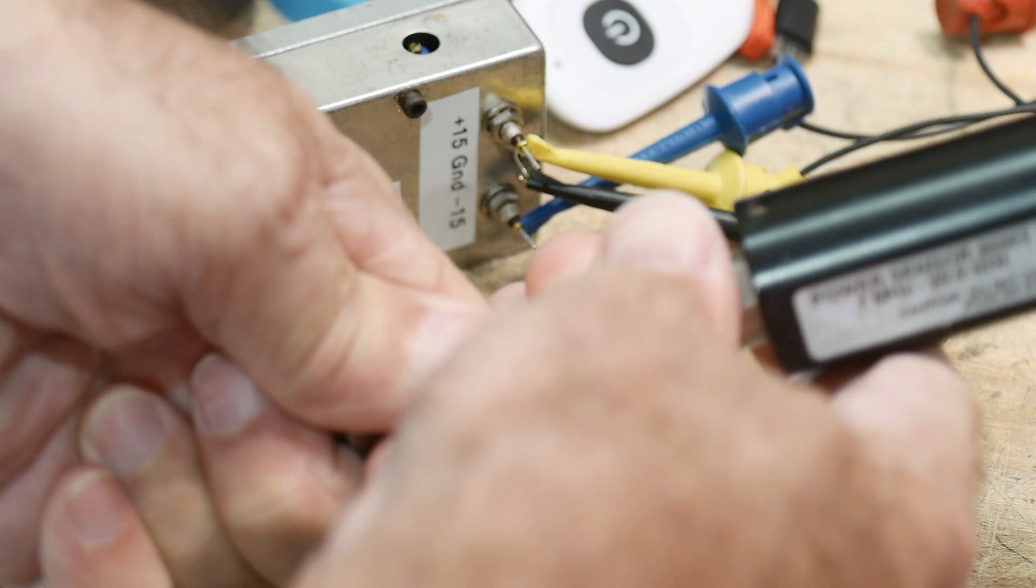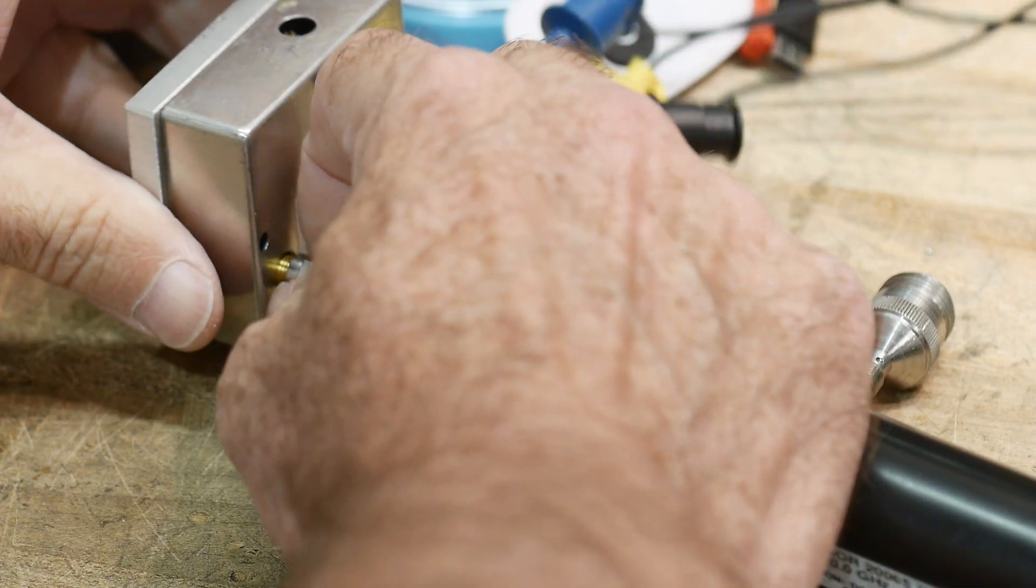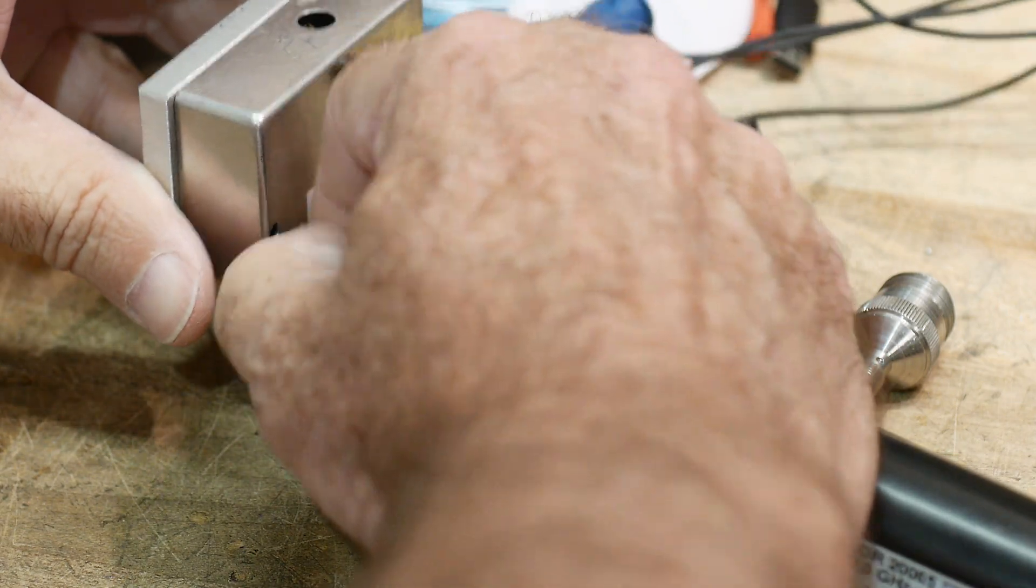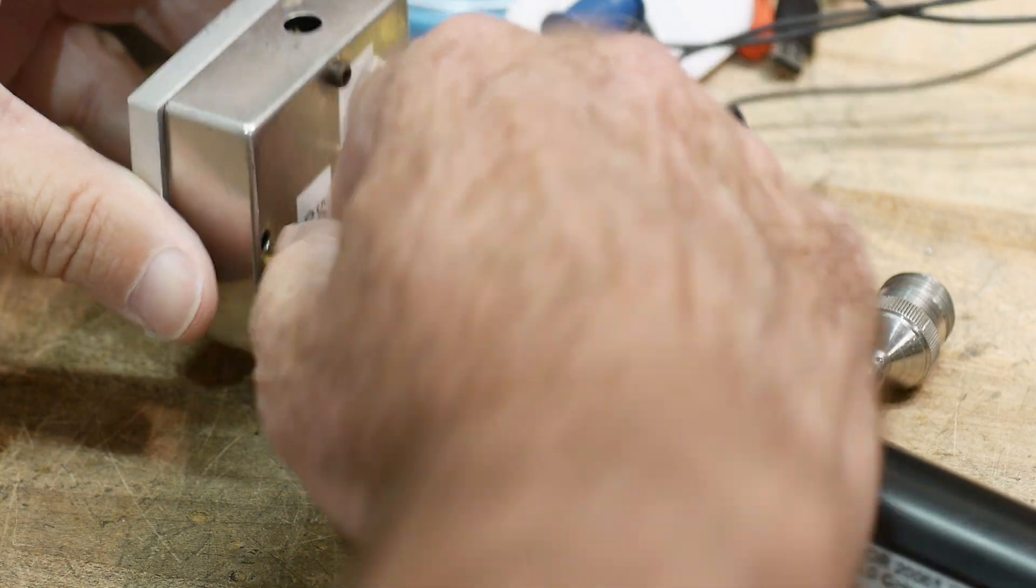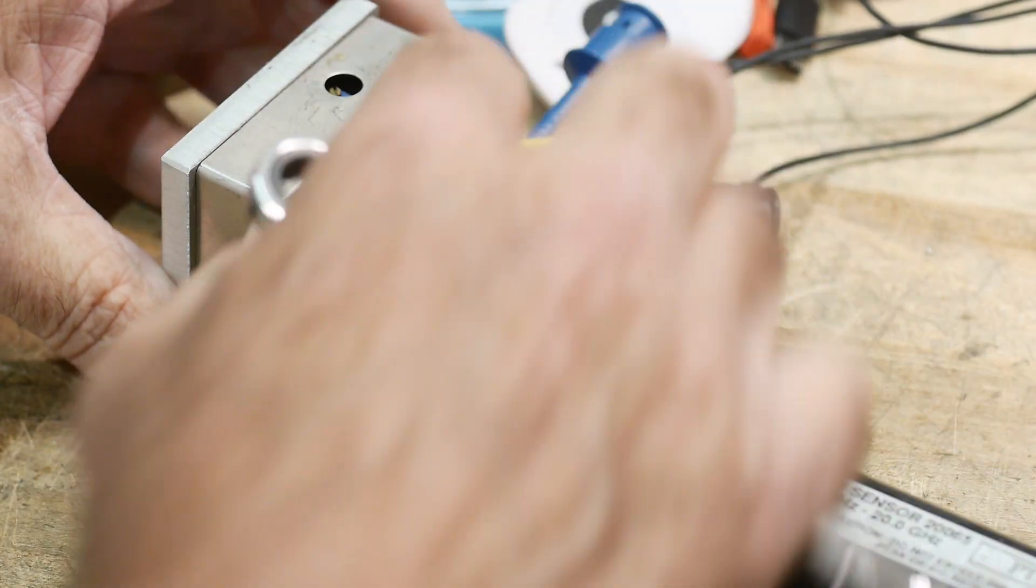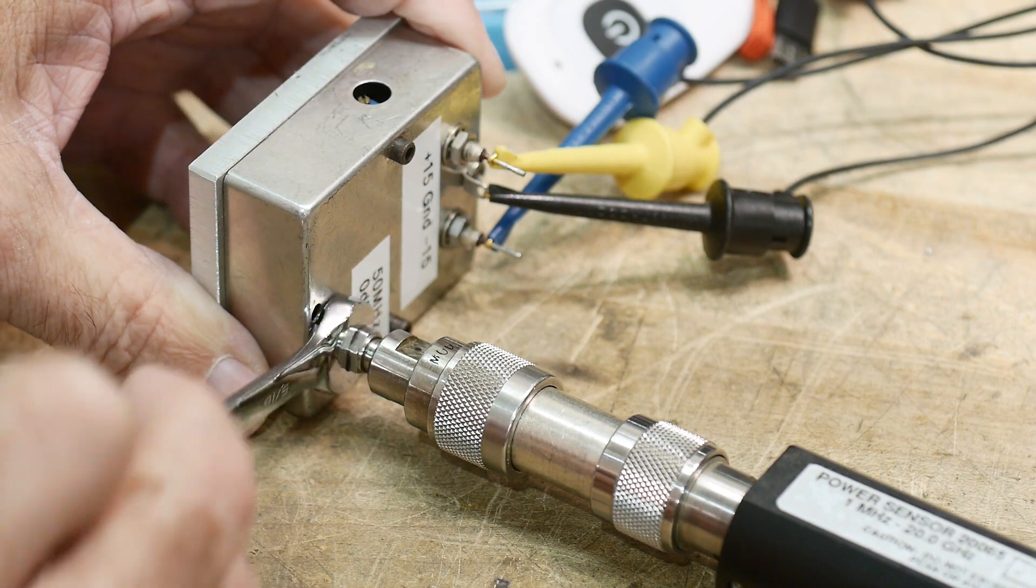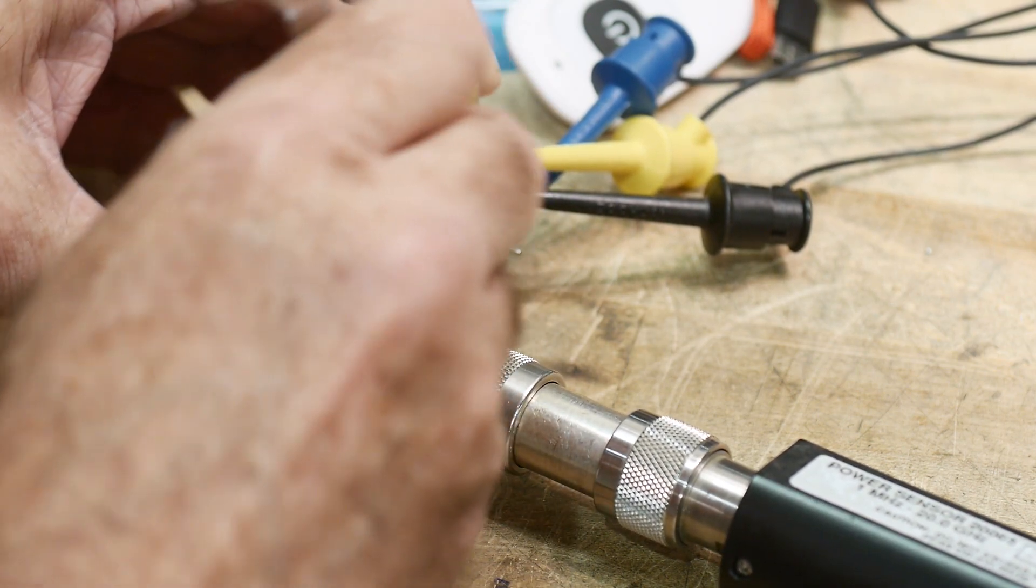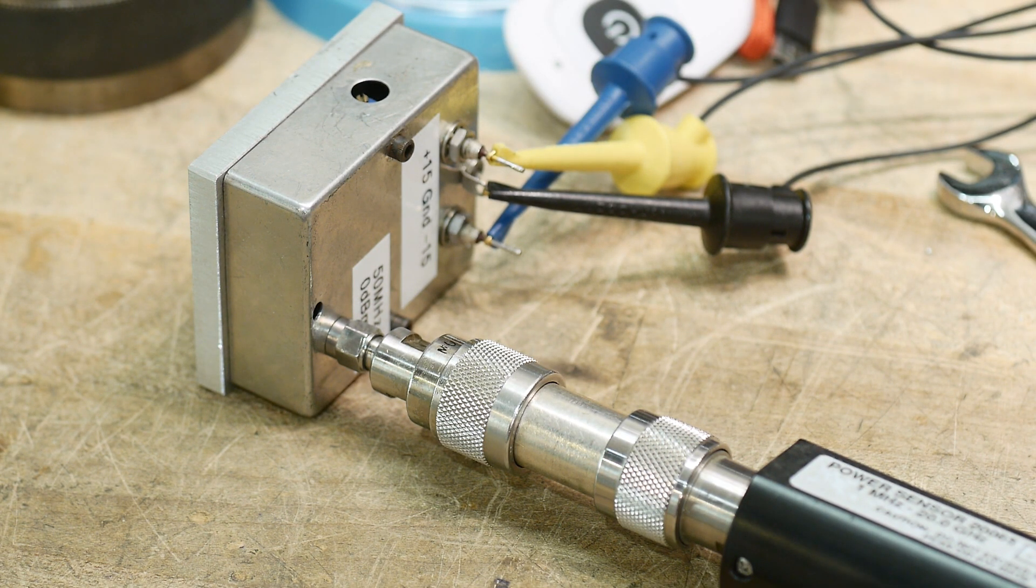I'm going to attach the power sensor. Now the problem with all of this is you've got all of this mass. Luckily we're measuring a very small thing, but a lot of times you're measuring big things and you have to really worry about torquing off little connectors and ruining things. Especially 3.5 millimeter connectors which are super expensive. But luckily this is really light. We are going to connect this up. It's about tight. Now we're going to go back to the power meter.